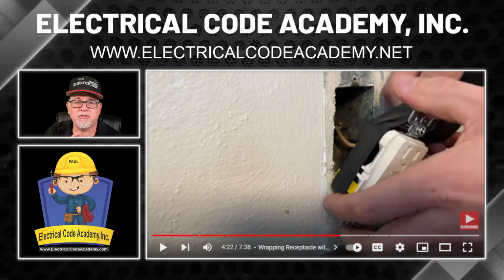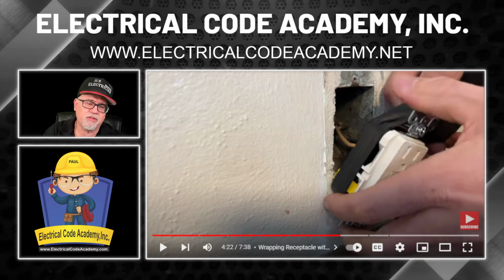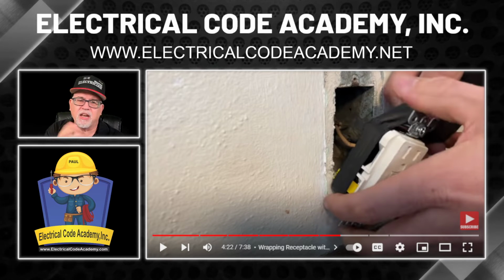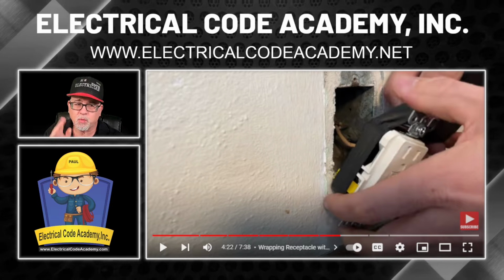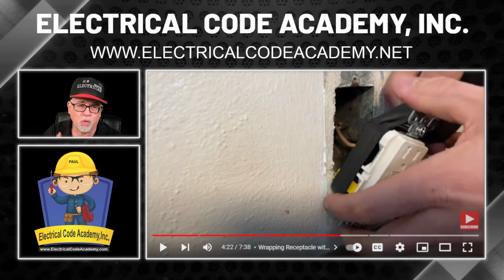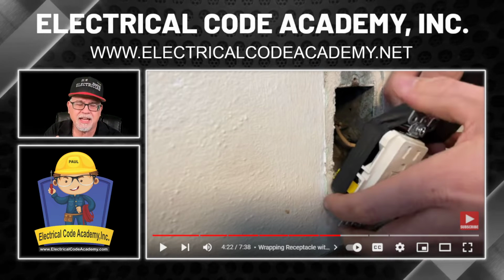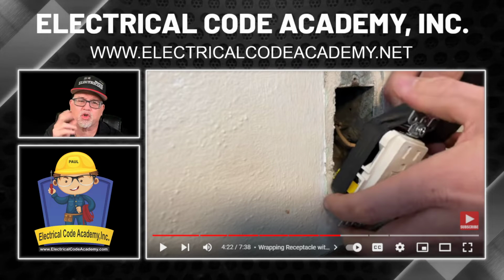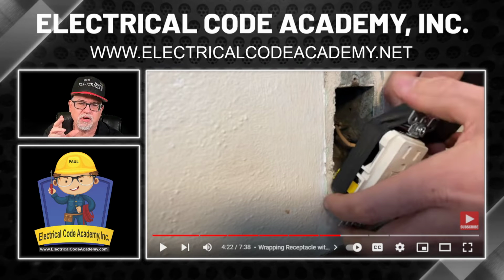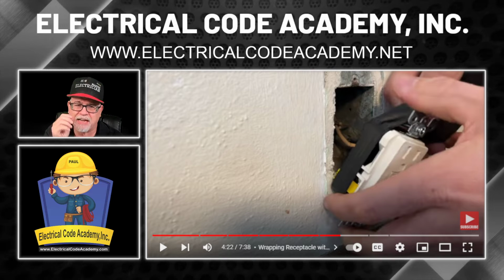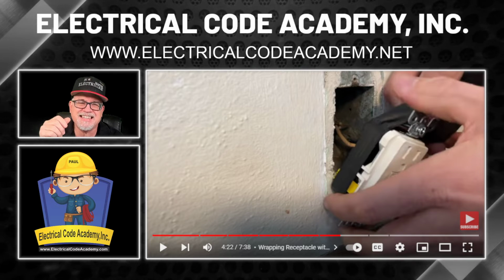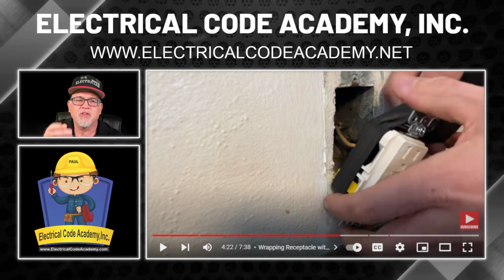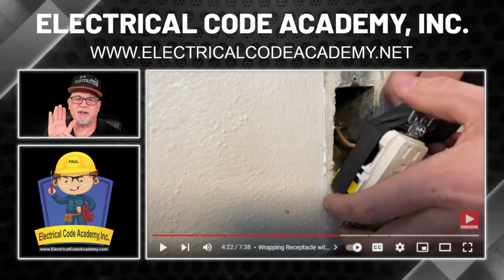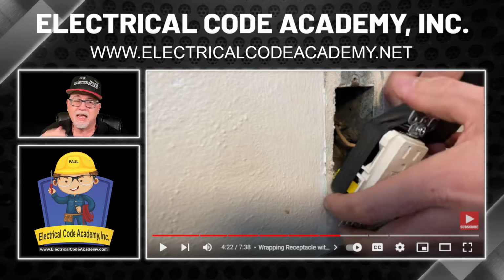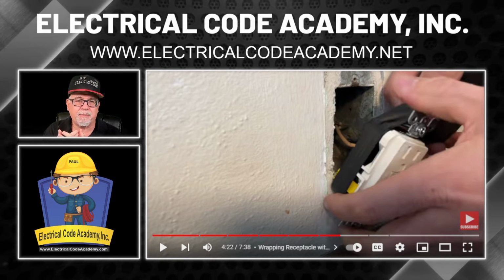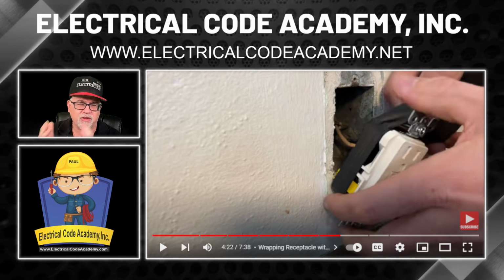Okay. I'll also remind you, see how close he is to this wall with this device? And there's a lot of movement on those conductors. If this is one of the houses like I used to work in, that was the old knob or the old cloth, it would start to brittle and crack with even those movements. So once I take that first device off, I usually would splice on pigtails and then neatly get those conductors back so that all I'm working with is those fresh conductors. It only takes a second. That's just me, because usually what happened, it was nothing about the terminals touching the metal box.